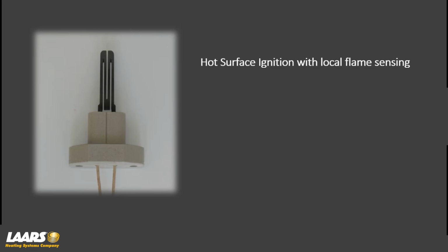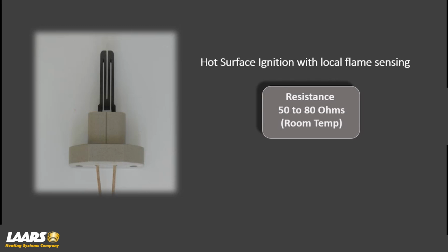So the gas valve gets energized for 4 seconds. If it does not see that flame rectification, it will not allow it to light. It'll drop back out. Non-CSD1 will try again. CSD1 will lock out. That's a single try for ignition. We'll go through that as well. So Norton makes the igniter, and Norton tells you that resistance to check an igniter would be 50 to 80 ohms. But that's at room temperature.